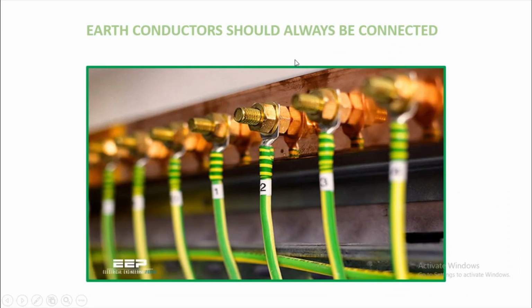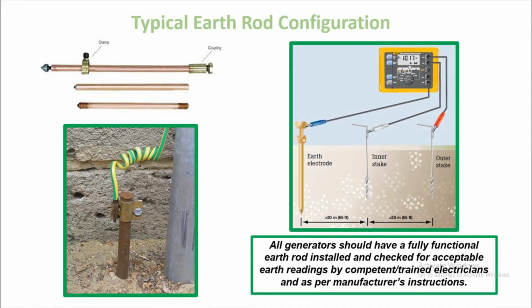Earth conductors should always be connected. So all earth conductors should be connected and not loose. So this should be inspected by our electrician periodically. Here are some pictures of typical earth rod configurations. So you can see here the copper earthing rods with the clamps or couplings, and green cables from the buildings connected to the earthing with clamps or couplings to ensure that there is a proper flow of electrical current. And you can see here from the machines, all generators should have a fully functional earth rod installed and checked for acceptable earth readings by a competent trained electrician as per manufacturer instructions.